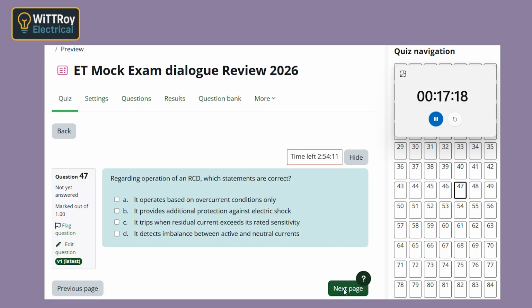Question 47. Regarding operation of an RCD, which statements are correct? I know an RCD is something to do with shock protection, but I still mix it up with overload sometimes. Good, let's sort that out properly. An RCD works by comparing the current going out on the active with the current coming back on the neutral. So it's checking whether the current going out matches the current coming back?